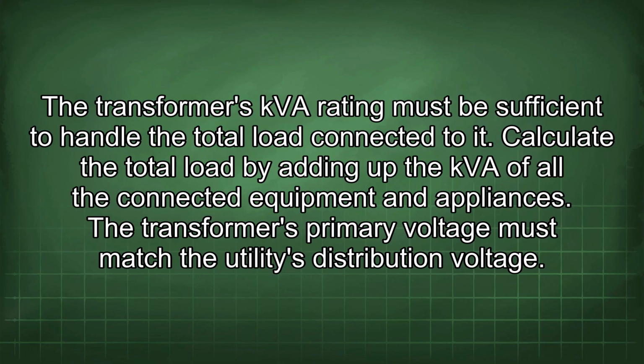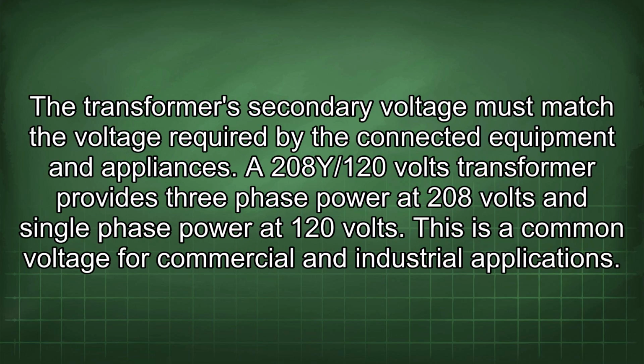The transformer's kVA rating must be sufficient to handle the total load connected to it. Calculate the total load by adding up the kVA of all the connected equipment and appliances. The transformer's primary voltage must match the utility's distribution voltage. The transformer's secondary voltage must match the voltage required by the connected equipment and appliances.